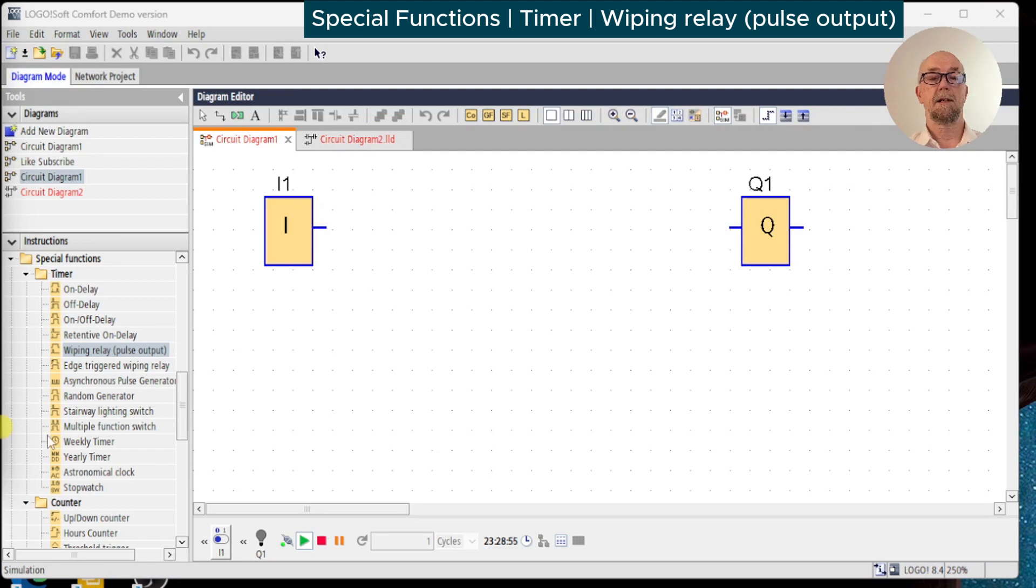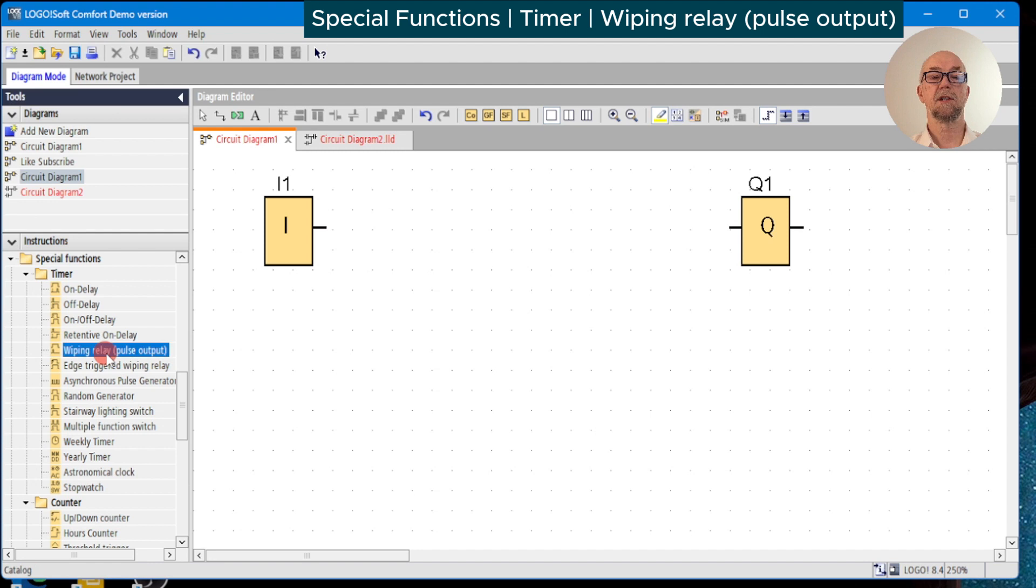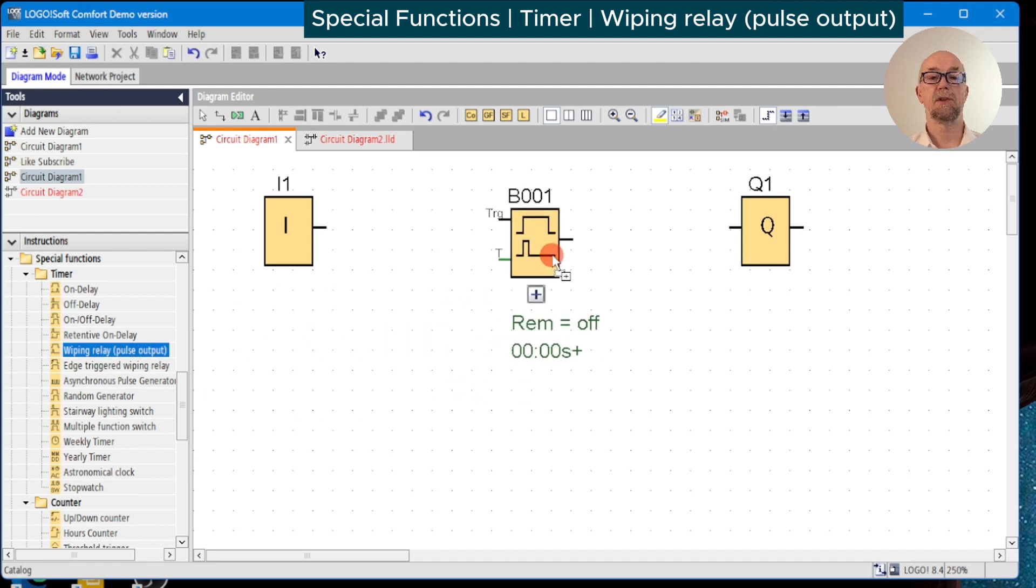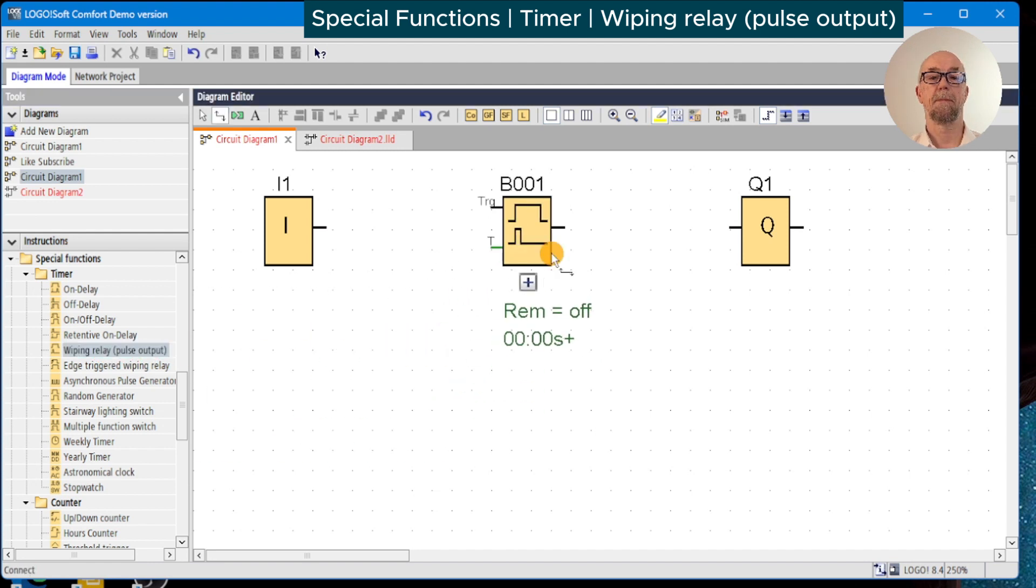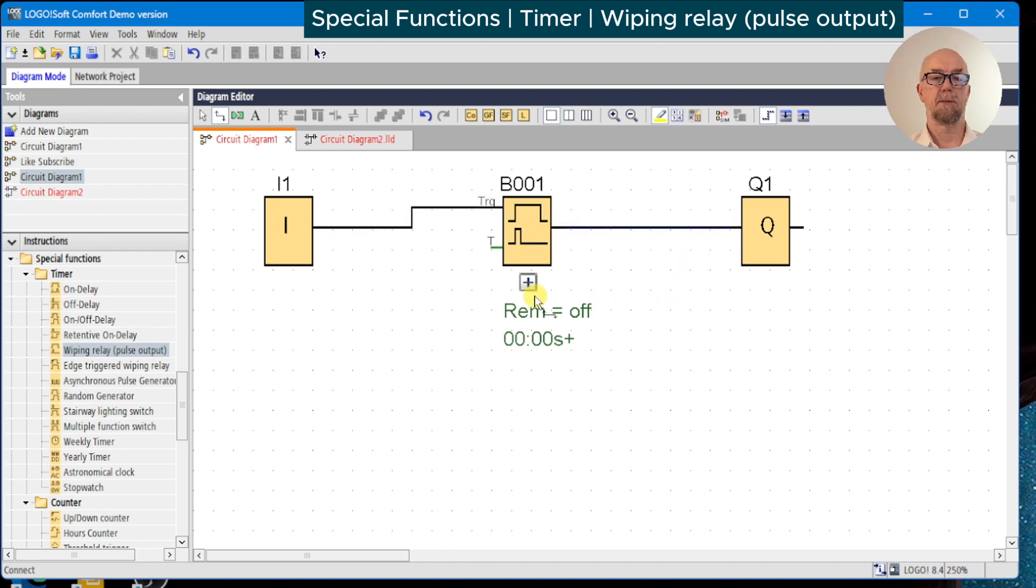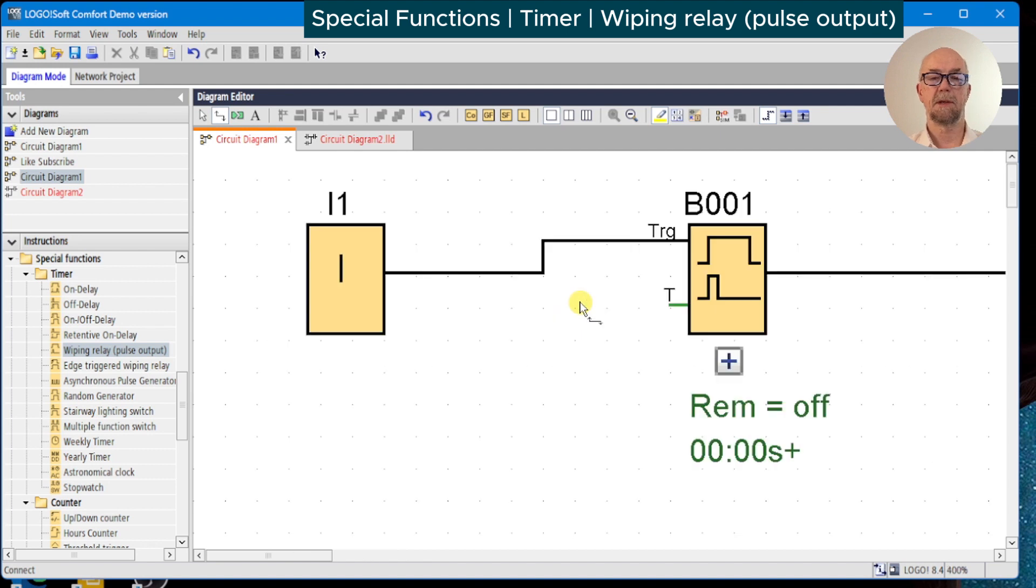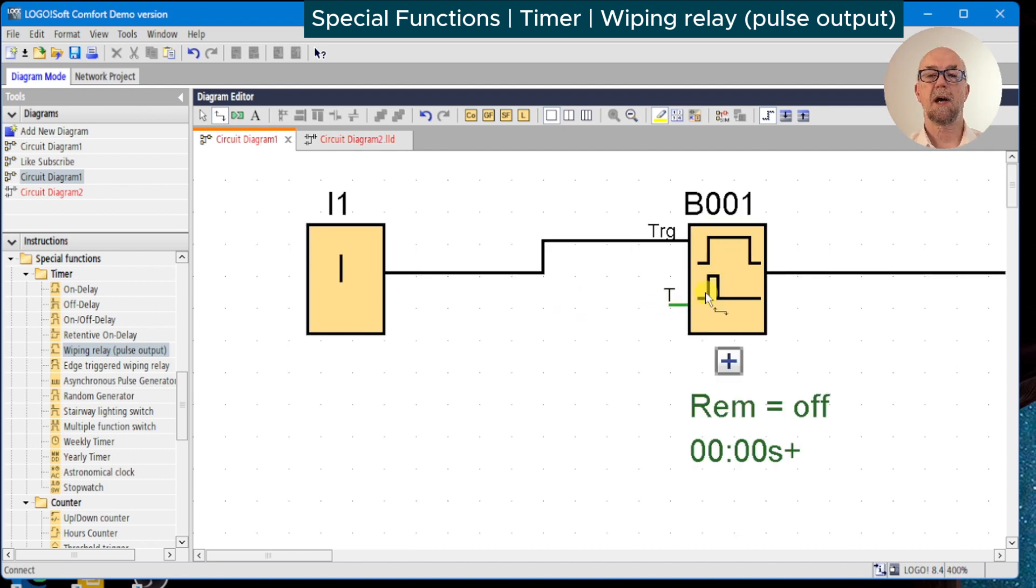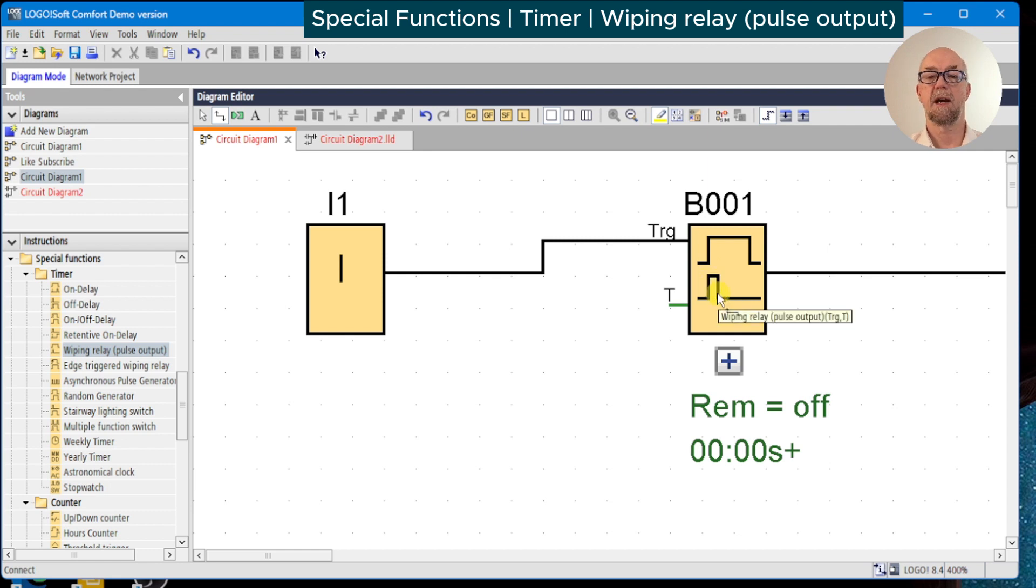The next in our series of special function timer instructions is the wiping relay or pulse output. This has one input trigger, one output, and some parameters we can set. We notice from the timing diagram symbol that when the trigger goes high, the output will turn on and turn off with the preset time delay, regardless of how long the trigger remains on.